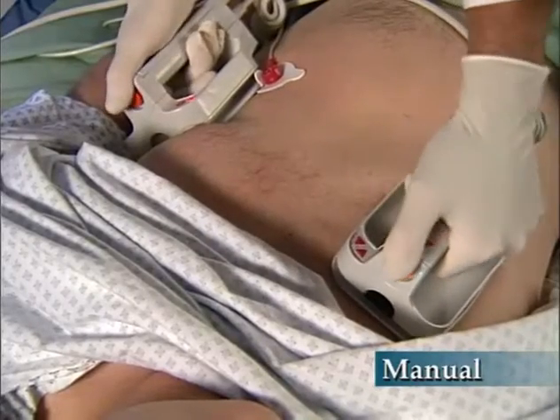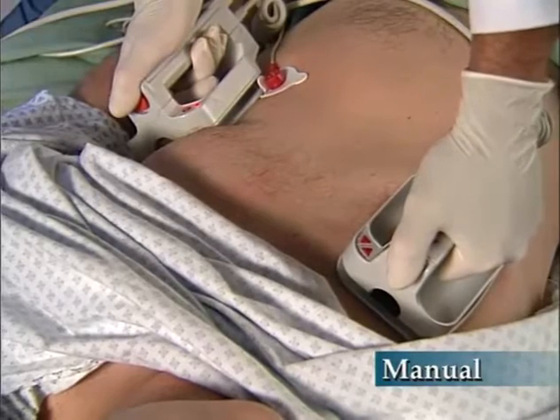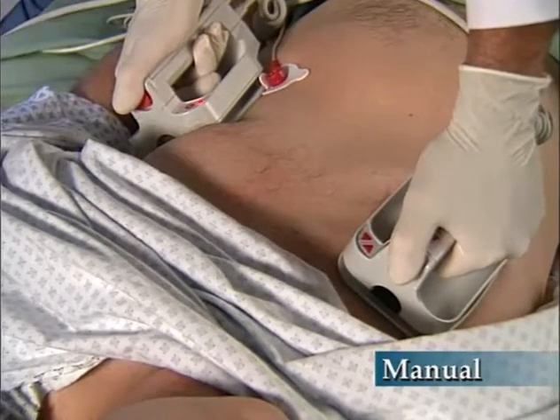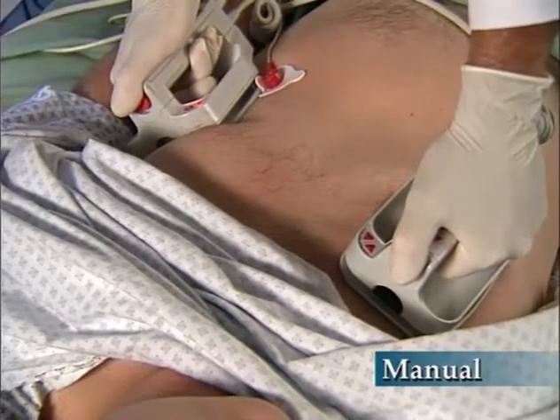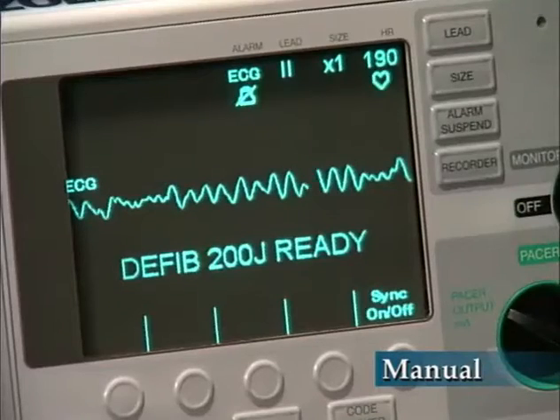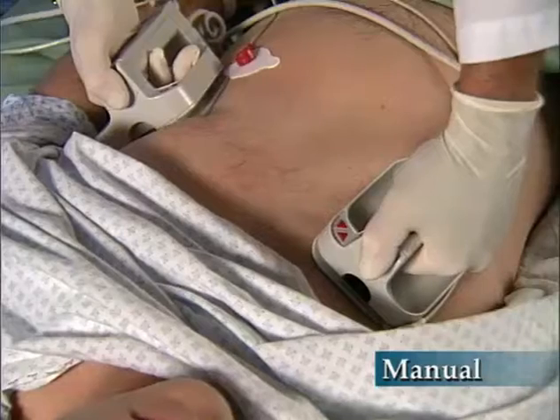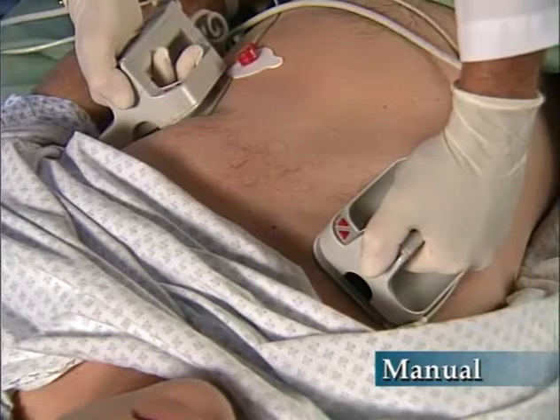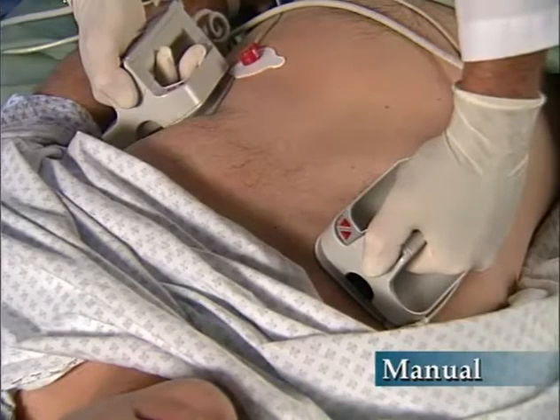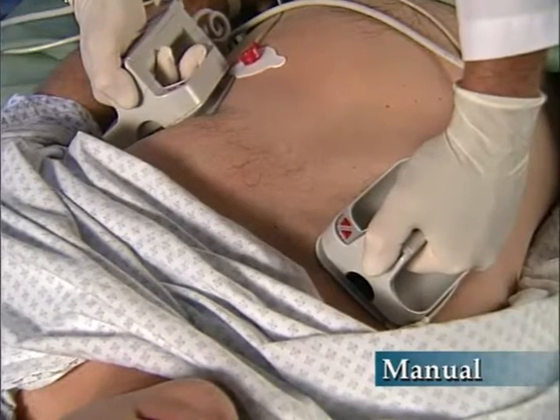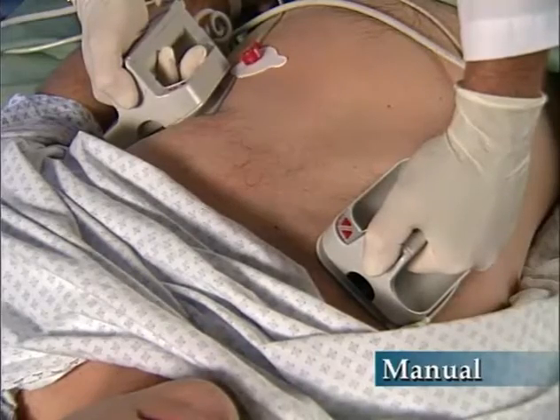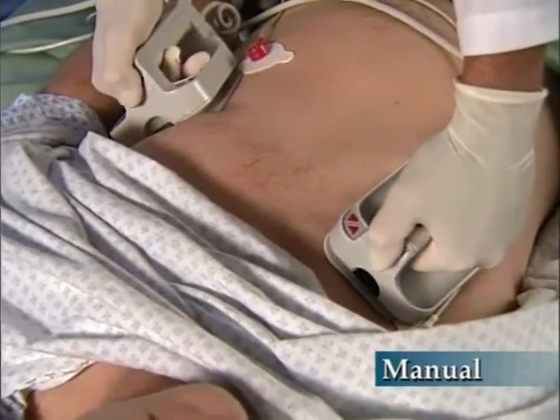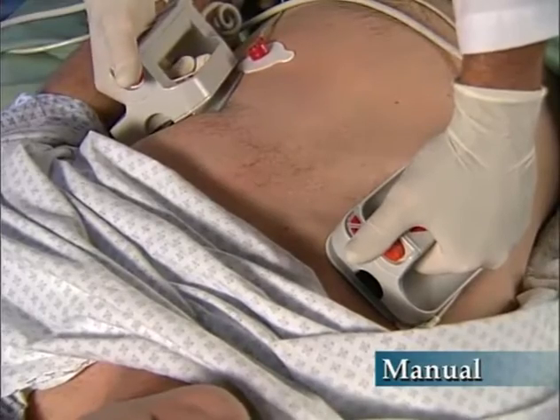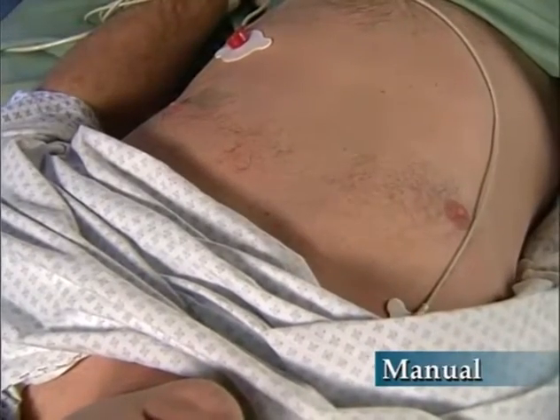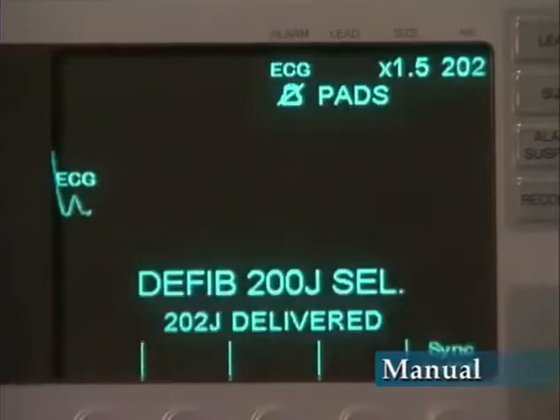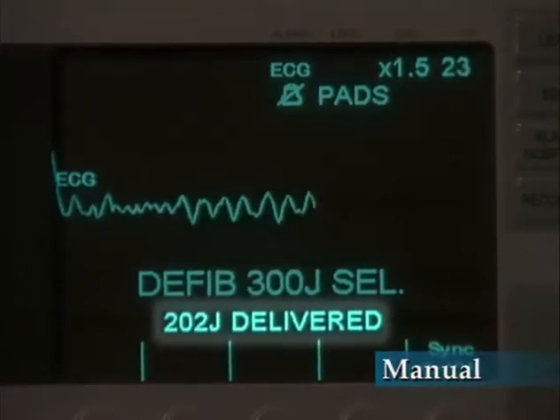After charging to the selected energy level, the charge indicator on the apex paddle will light. The charge-ready tone will sound, and the energy display will show ready and the selected energy level. Verify the energy level, warn all persons to stand clear prior to discharge, and observe all other safety procedures. Clear. Using your thumbs, depress and hold both shock buttons simultaneously until the energy is delivered to the patient. The display will show the amount of energy delivered.